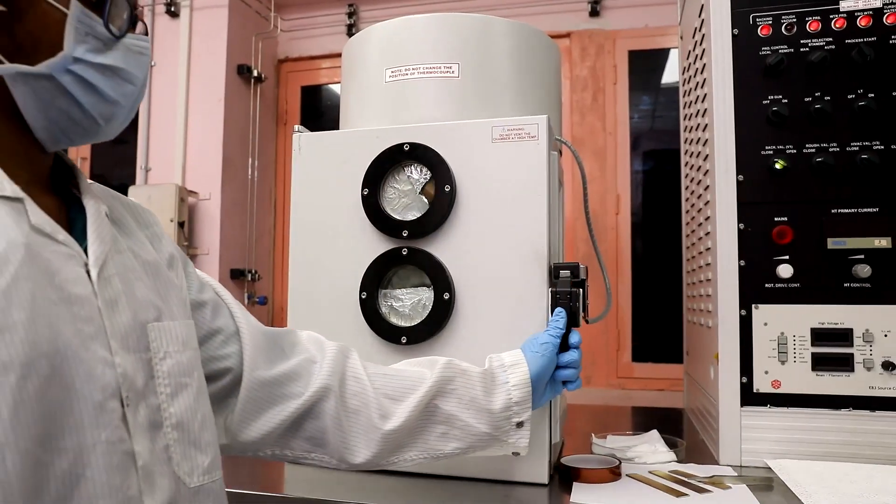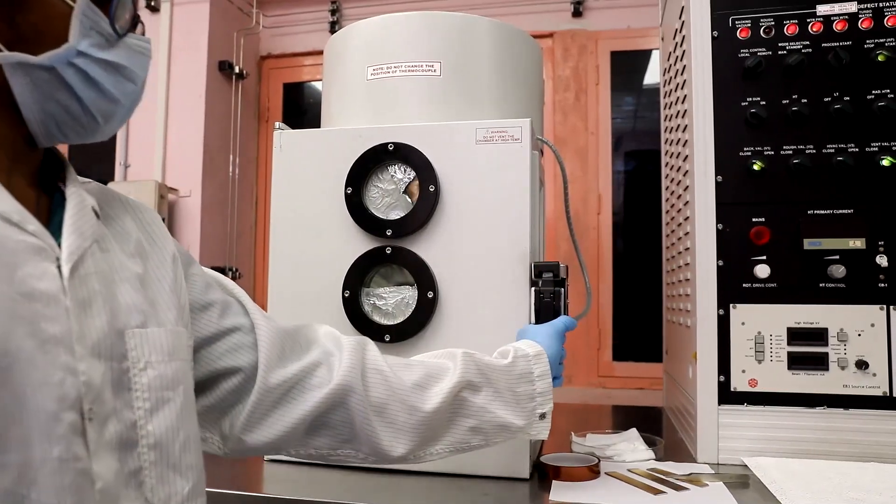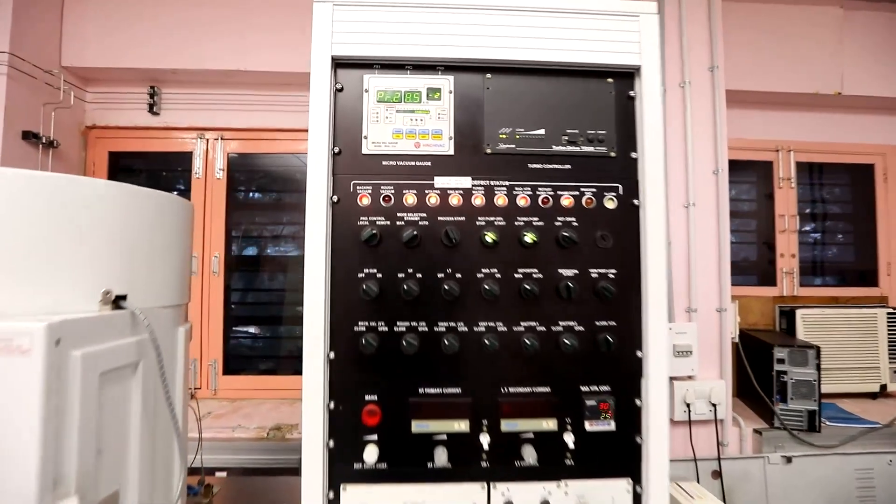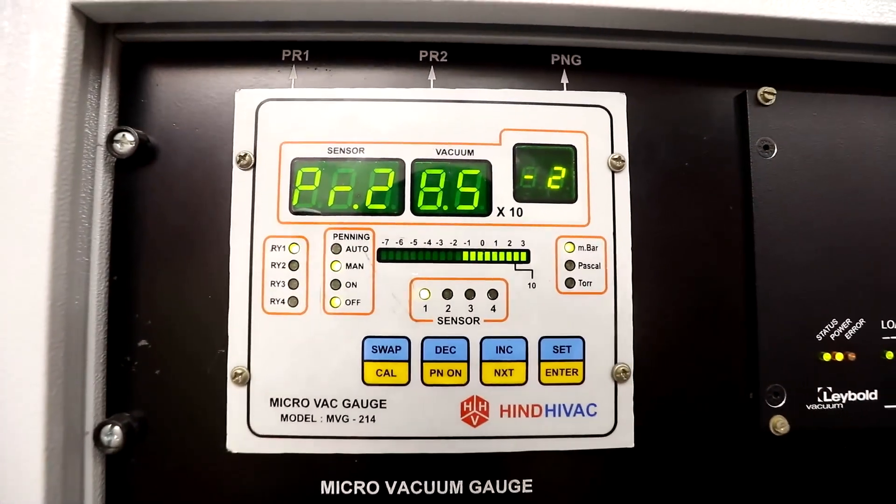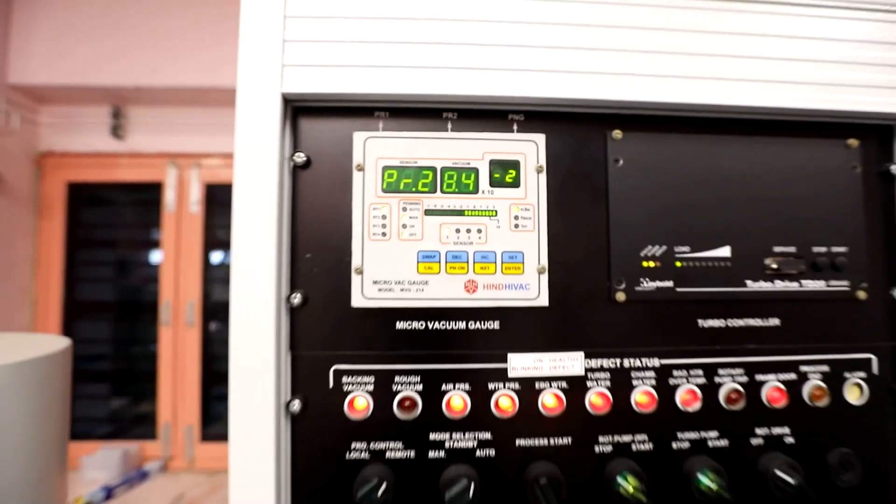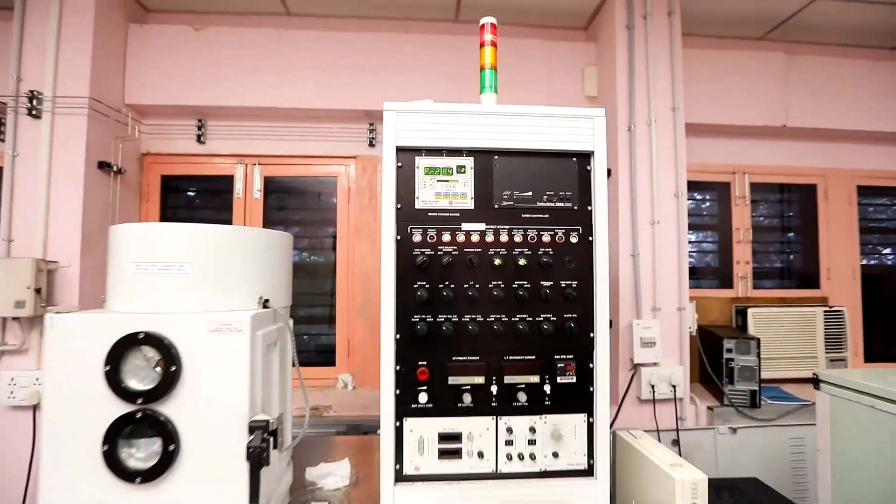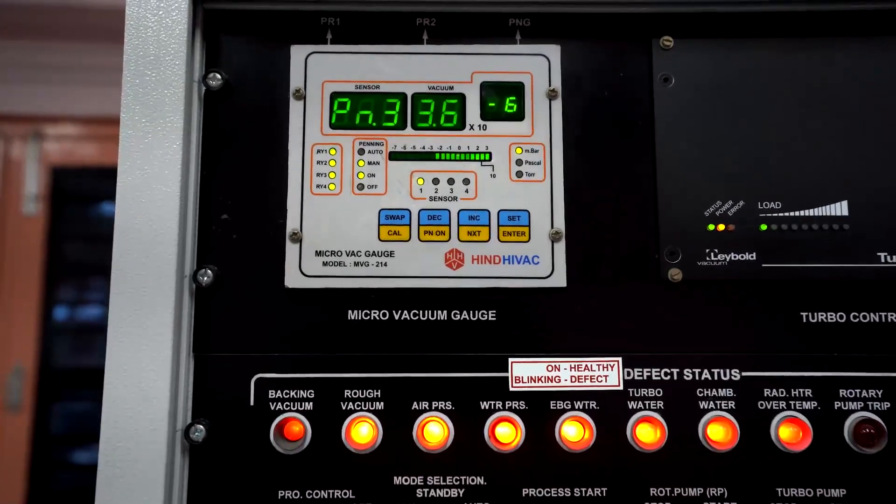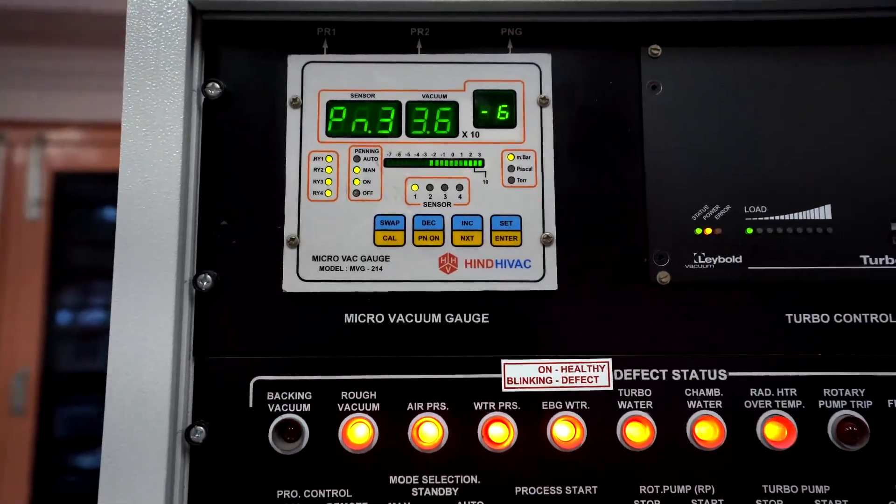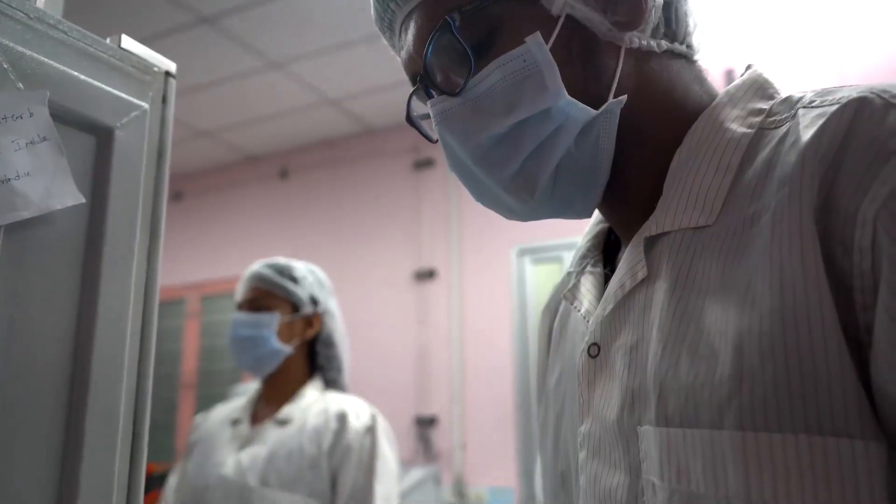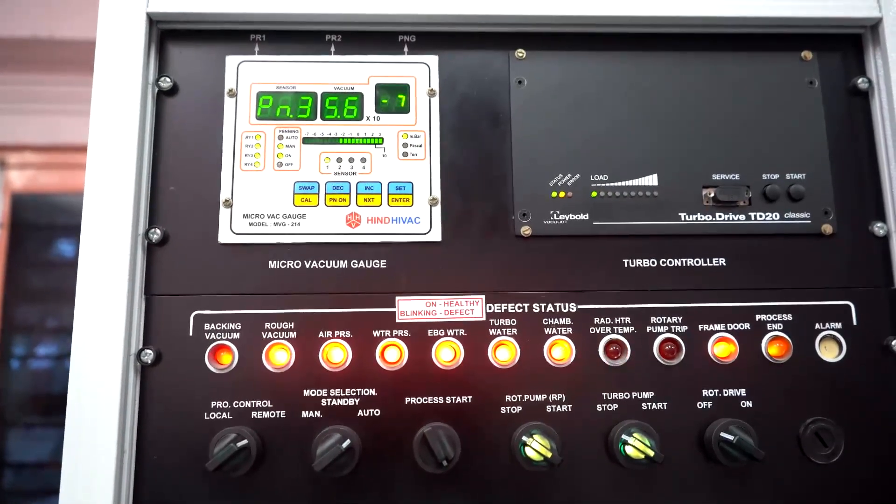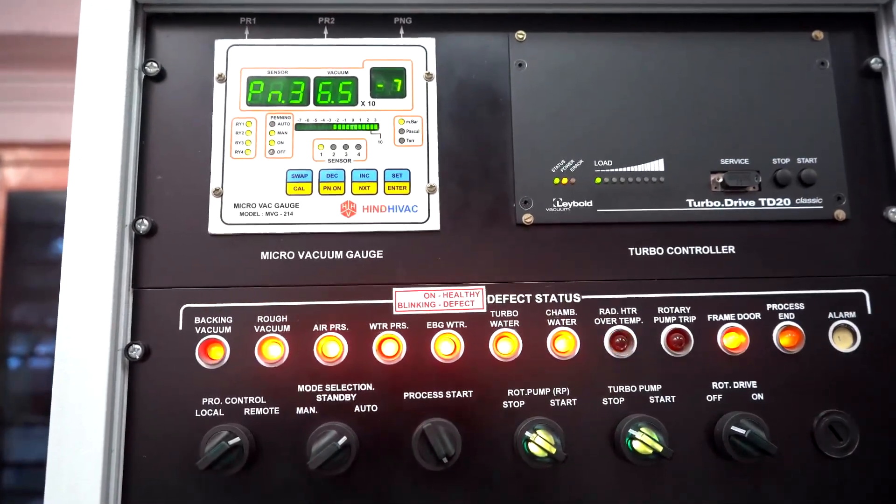Now close the chamber and start creating vacuum in the chamber. This starting vacuum is provided by the rotary pump till 10 to the power of minus 2 millibar, then higher vacuum is provided by the turbo pump. And when the vacuum reaches 3.5 into 10 to the power of minus 6 millibar range, we fill the liquid nitrogen and wait for a few minutes till it reaches around 6.5 into 10 to the power of minus 7 millibar.